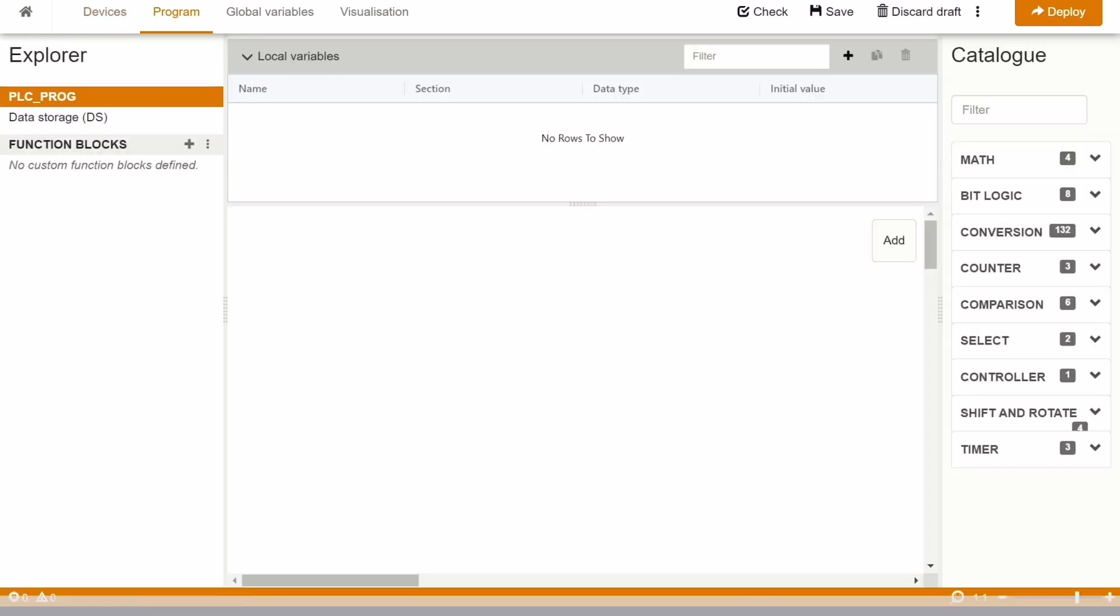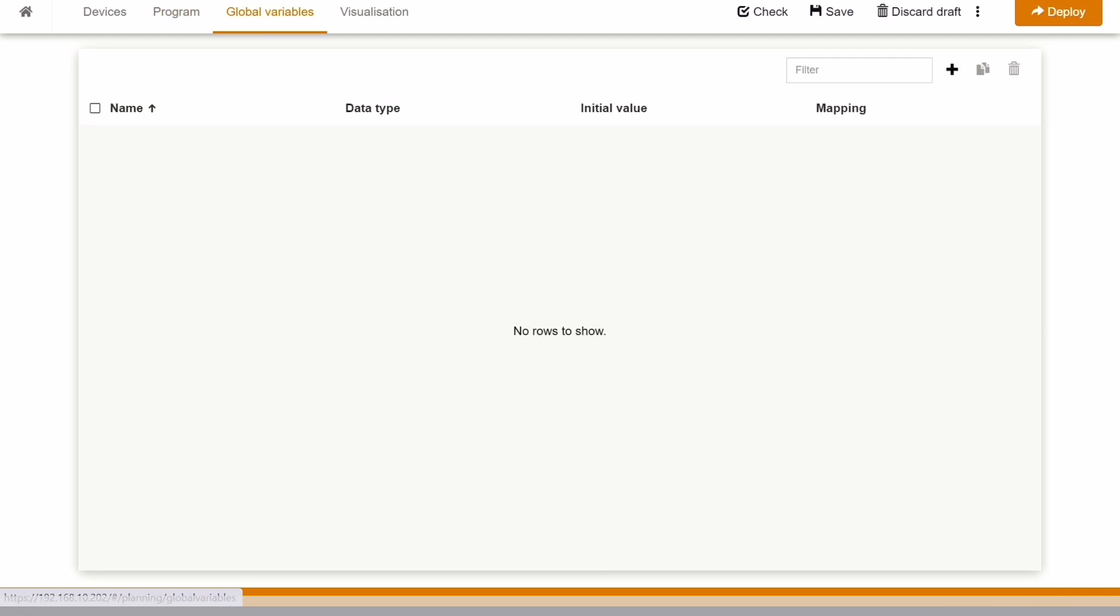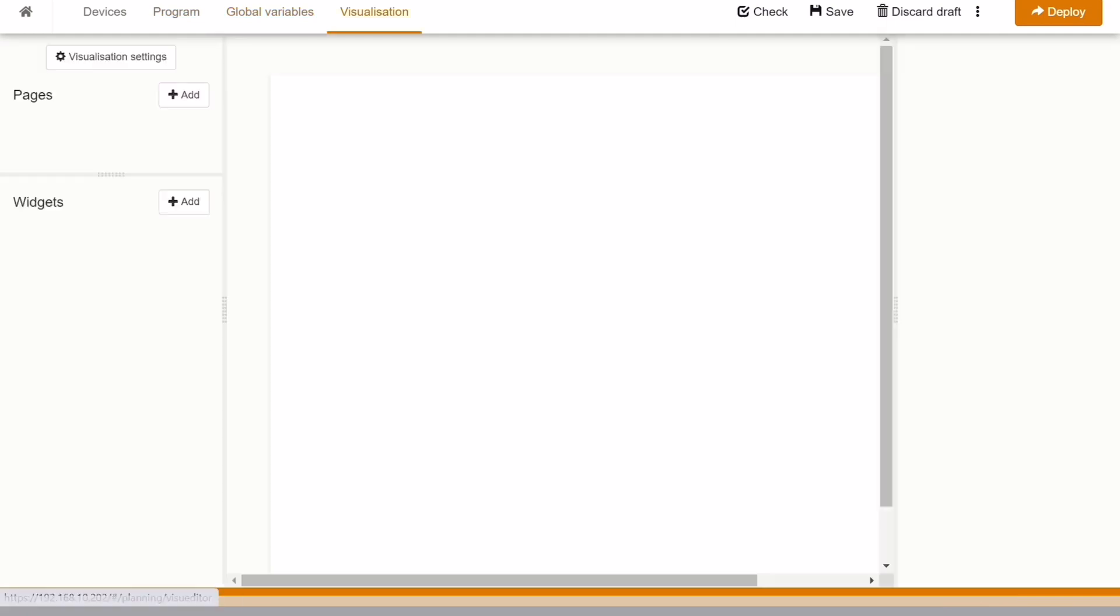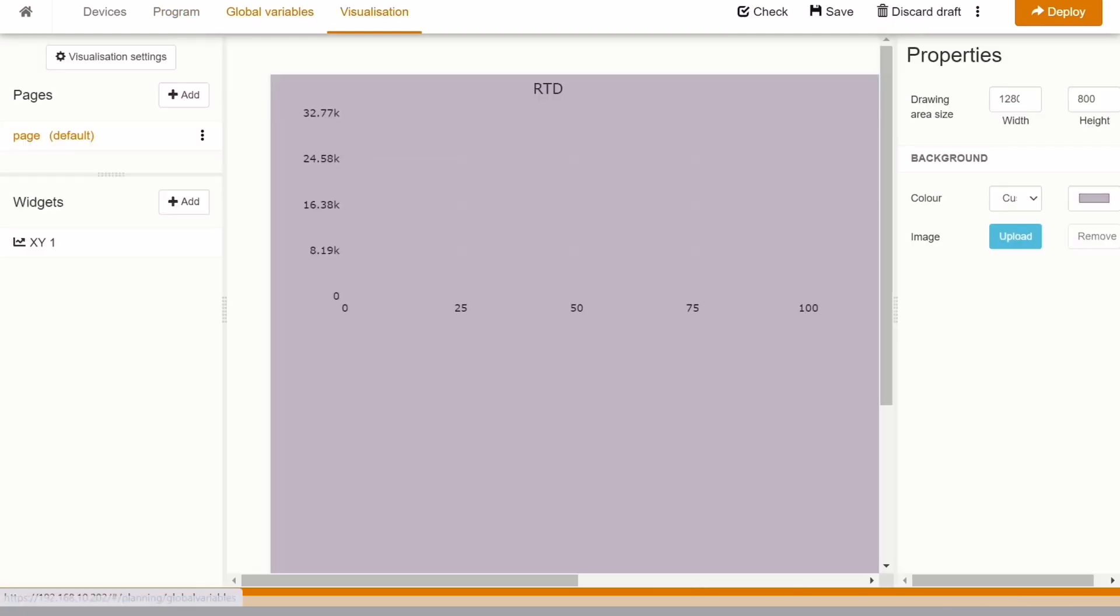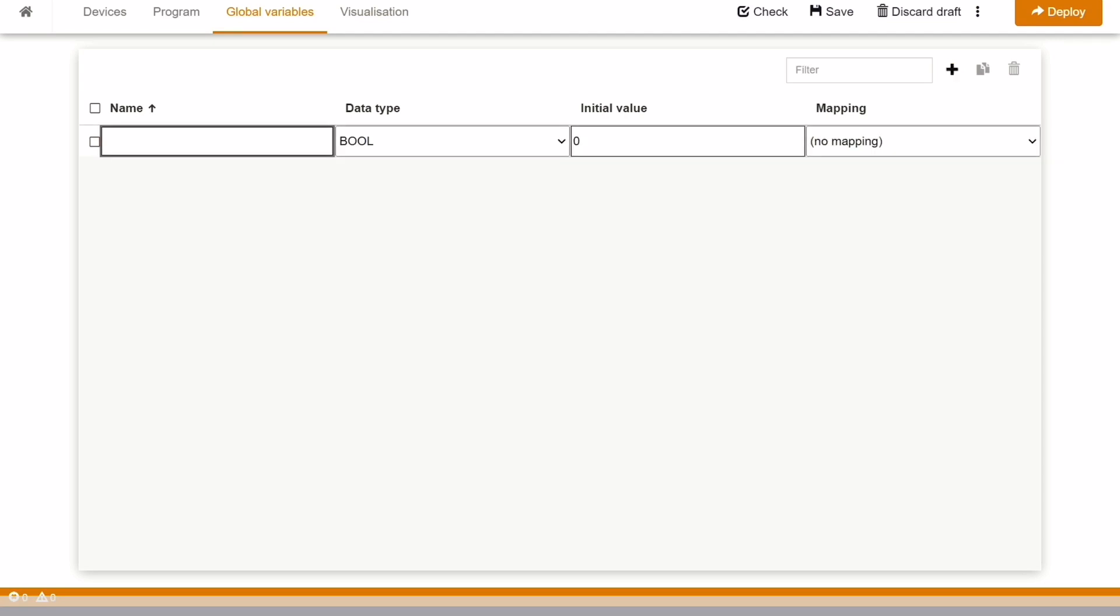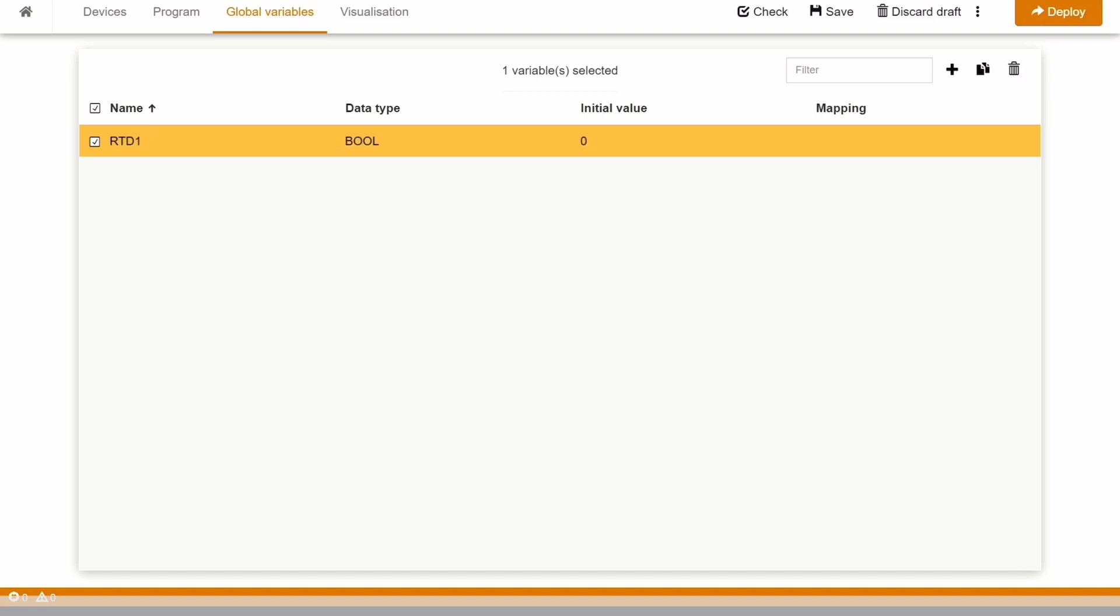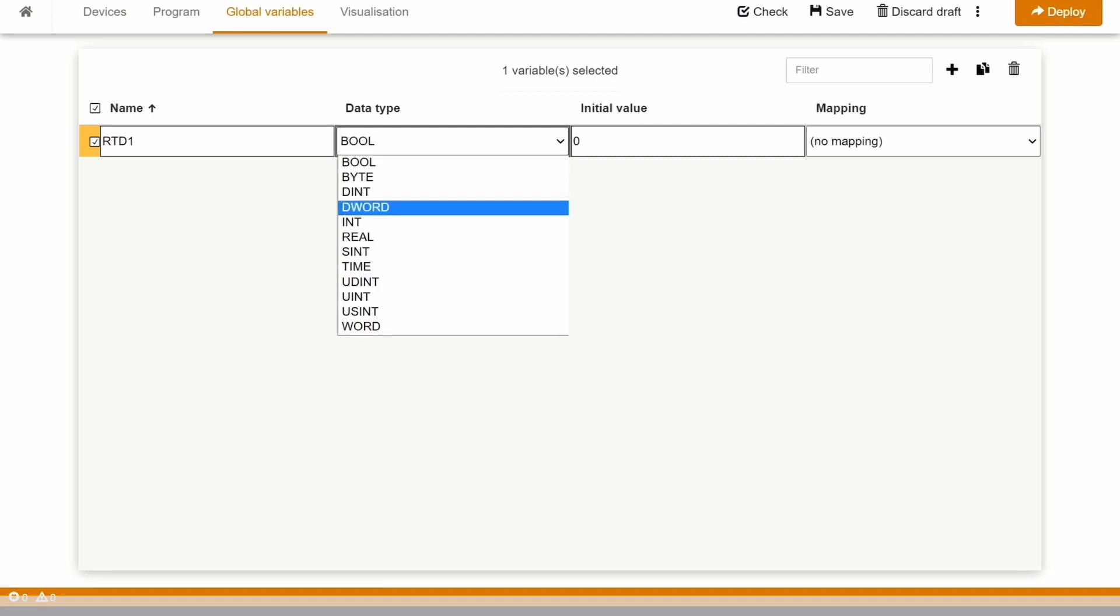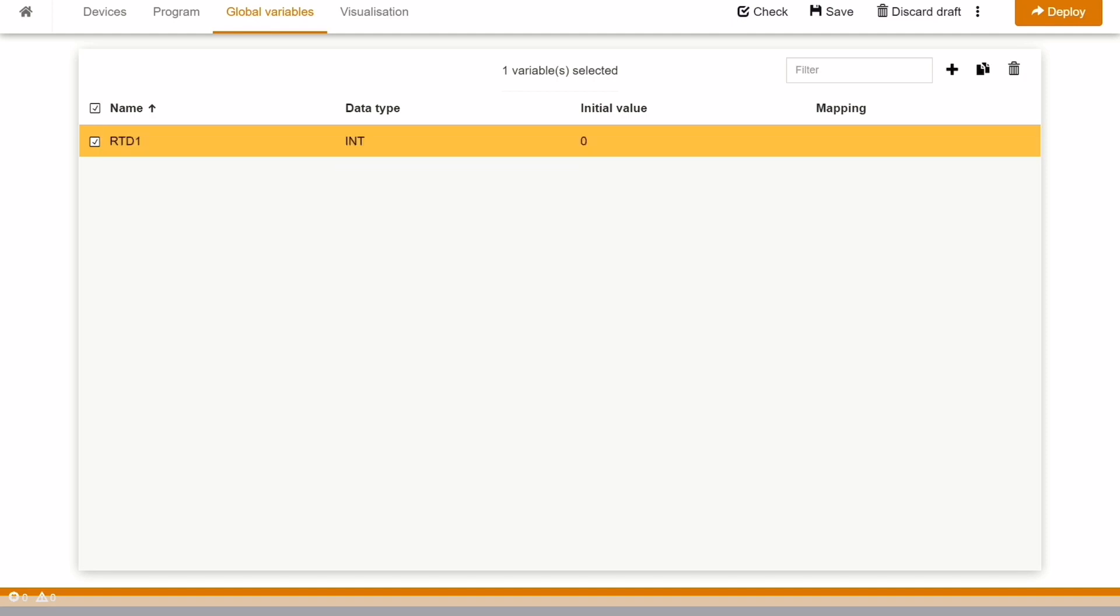In the program, we can program. In the global variable, we need to define all the global variable and the visualization. Let's first define the global variable, where we will define a variable with data type as integer and map it to the RTD channel so that we can read directly the values on this particular variable.